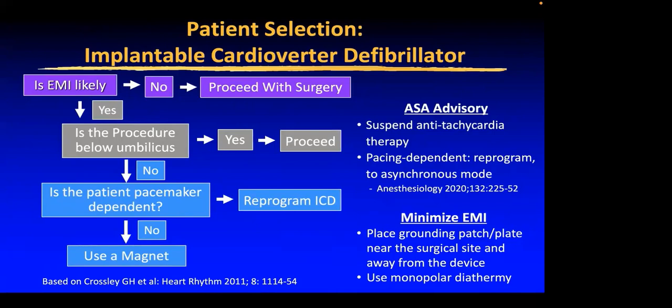Most importantly, in this patient population, it is imperative that we decrease the occurrence of EMI. This can be done by placing the grounding pad or plate very close to the surgical site and away from the ICD. Also, our surgeons should be advised to use bipolar diathermy as much as possible.